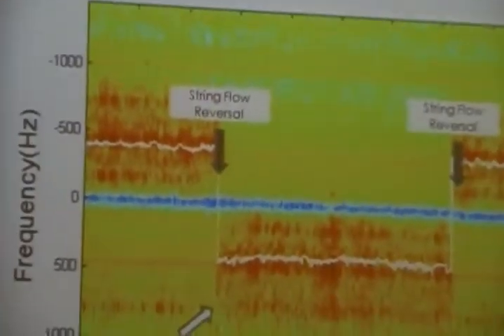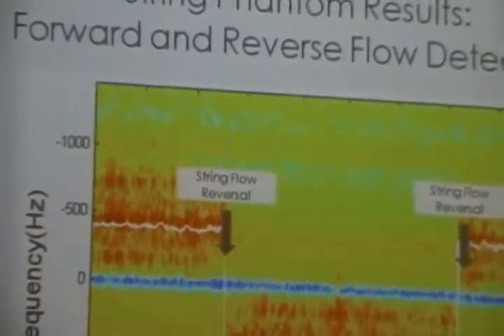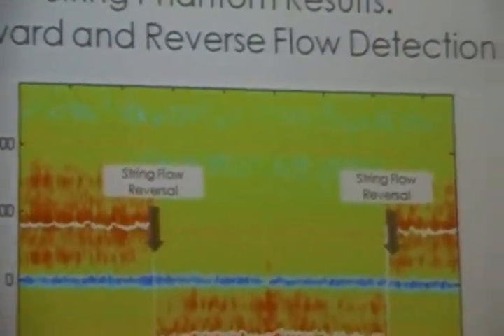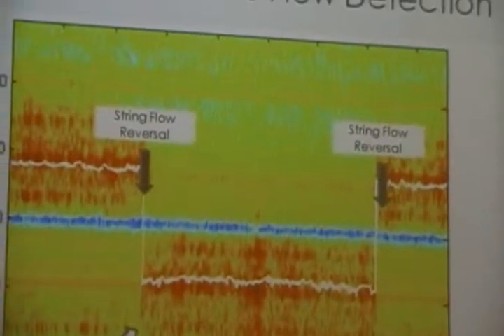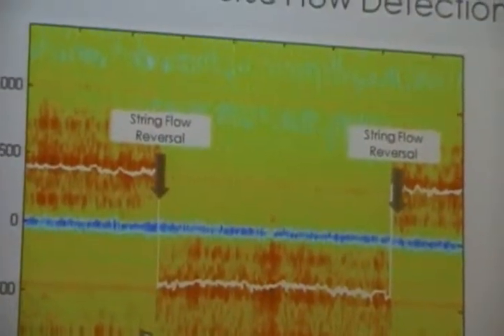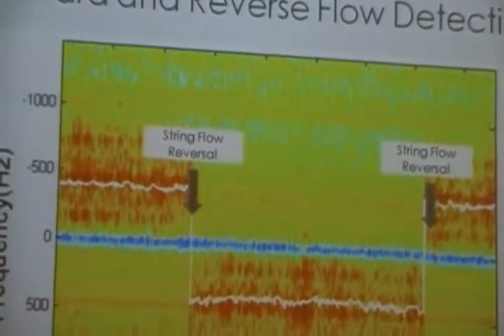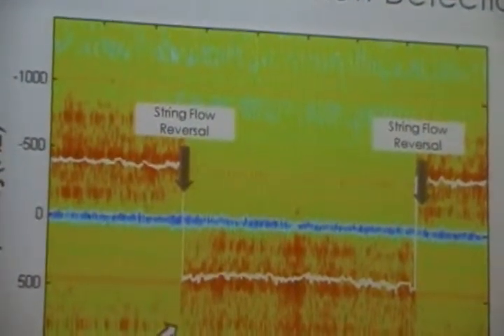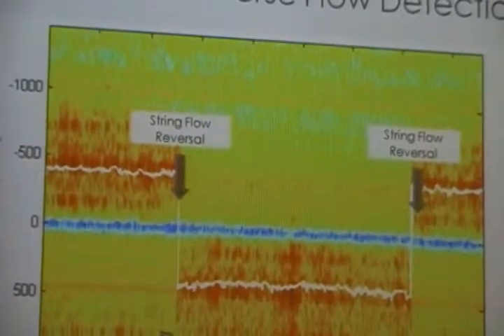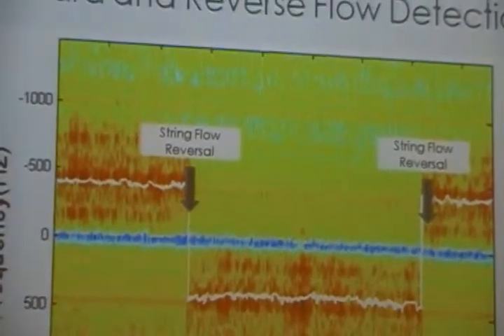When we introduced an instantaneous reversal in the string velocity, we were also able to see a shift in the measured Doppler, in the average frequency of the measured Doppler shift. So this allowed us to calculate velocity in both positive and negative directions.